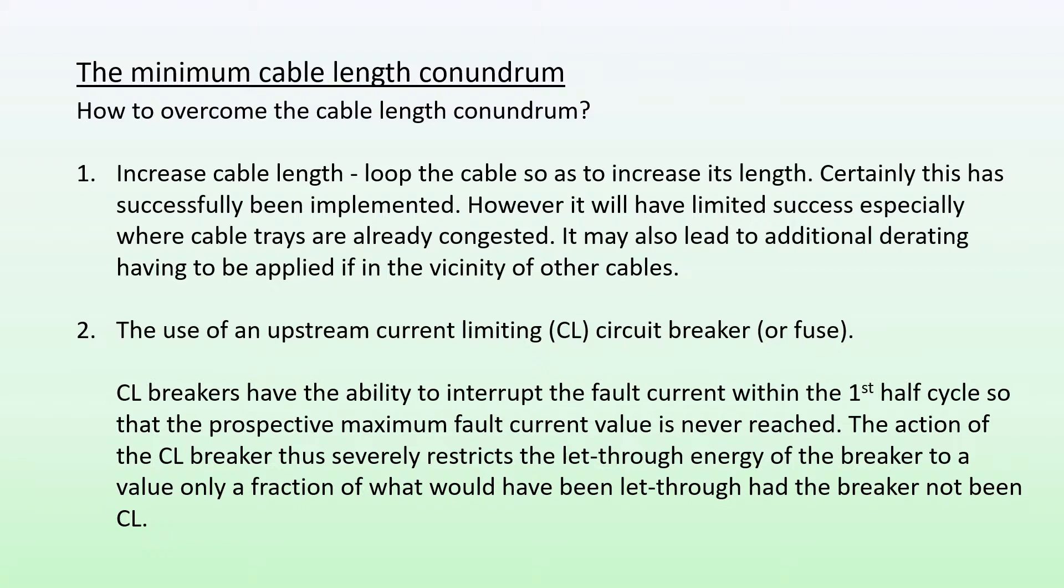The second option is the use of an upstream current limiting circuit breaker or fuse. Current limiting breakers have the ability to interrupt the fault current within the first half cycle so that the prospective maximum fault current value is never reached. The action of the current limiting breaker restricts the let-through energy of the breaker to a value only a fraction of what would have been the case had the breaker not been a current limiting one.